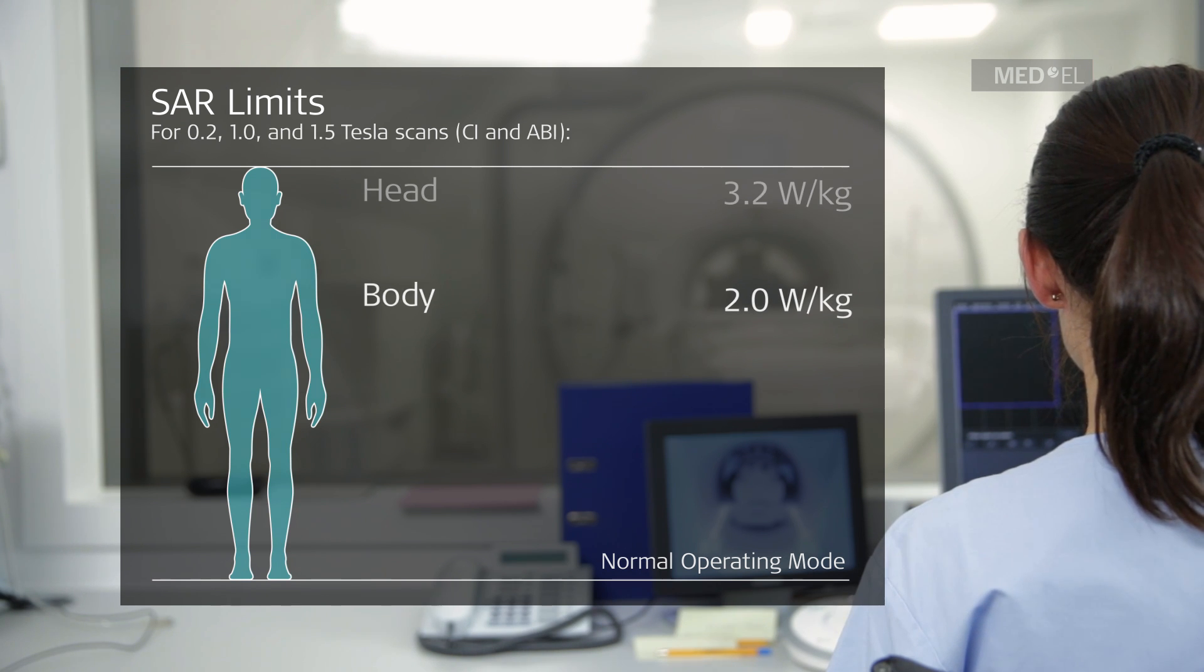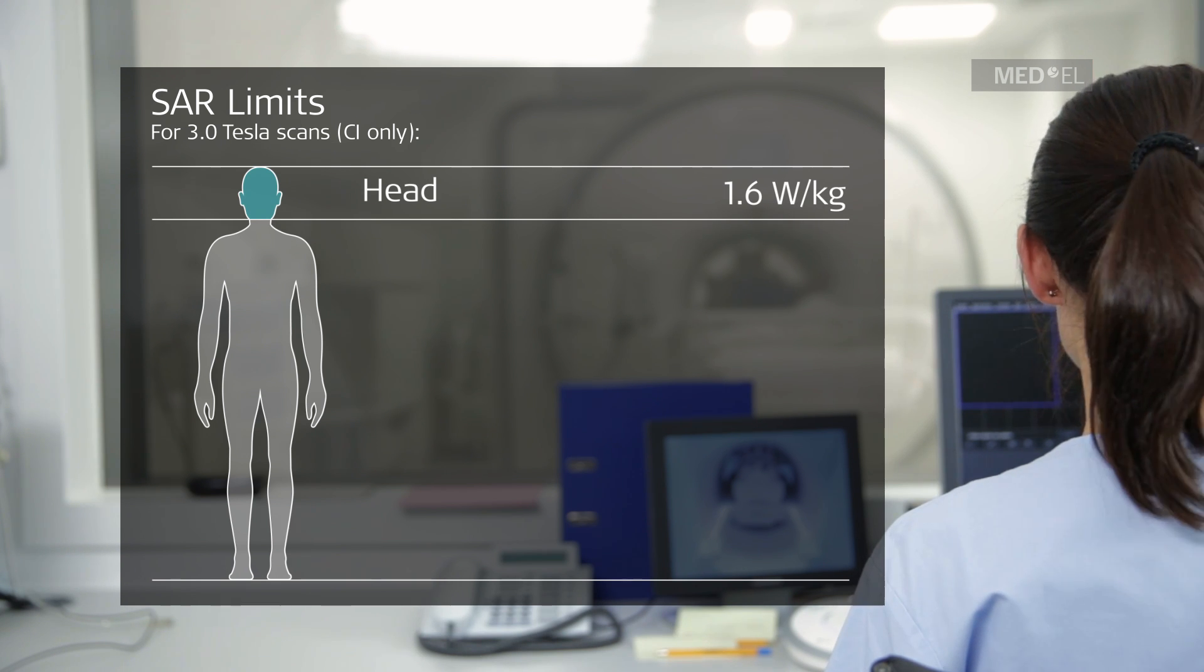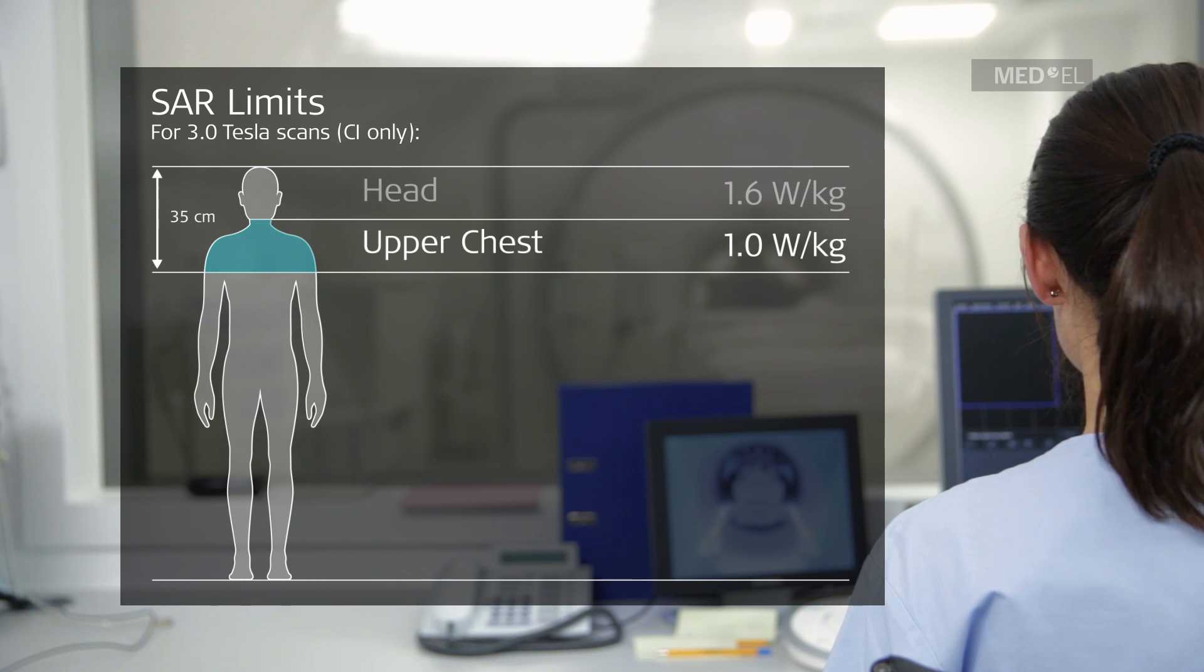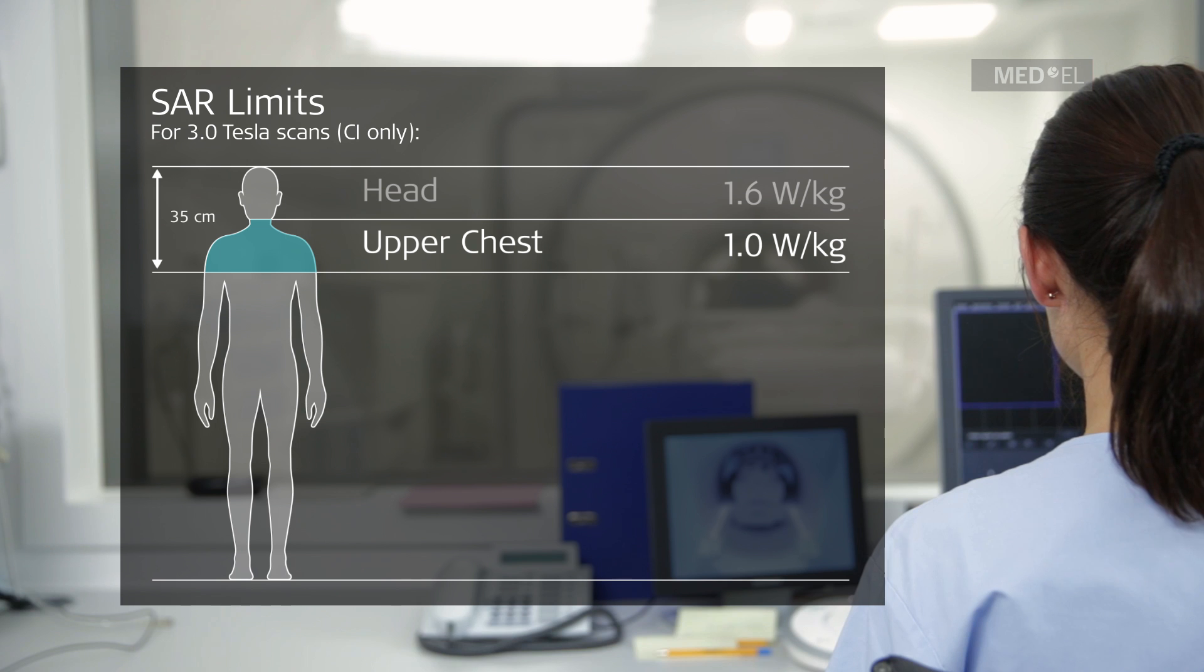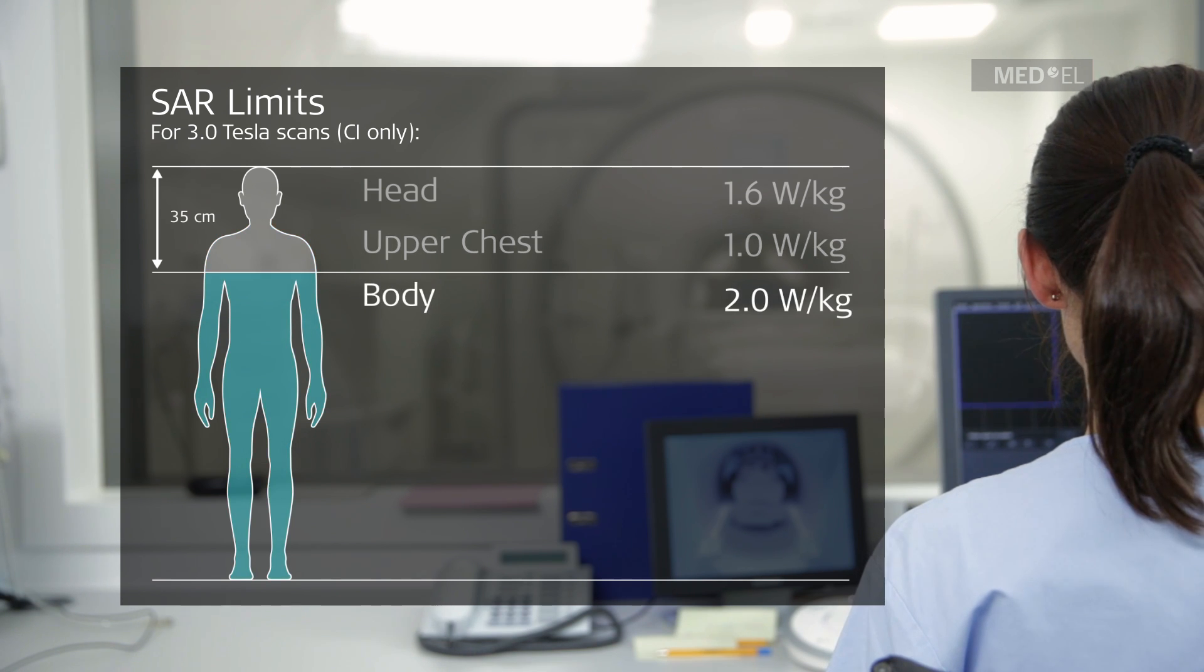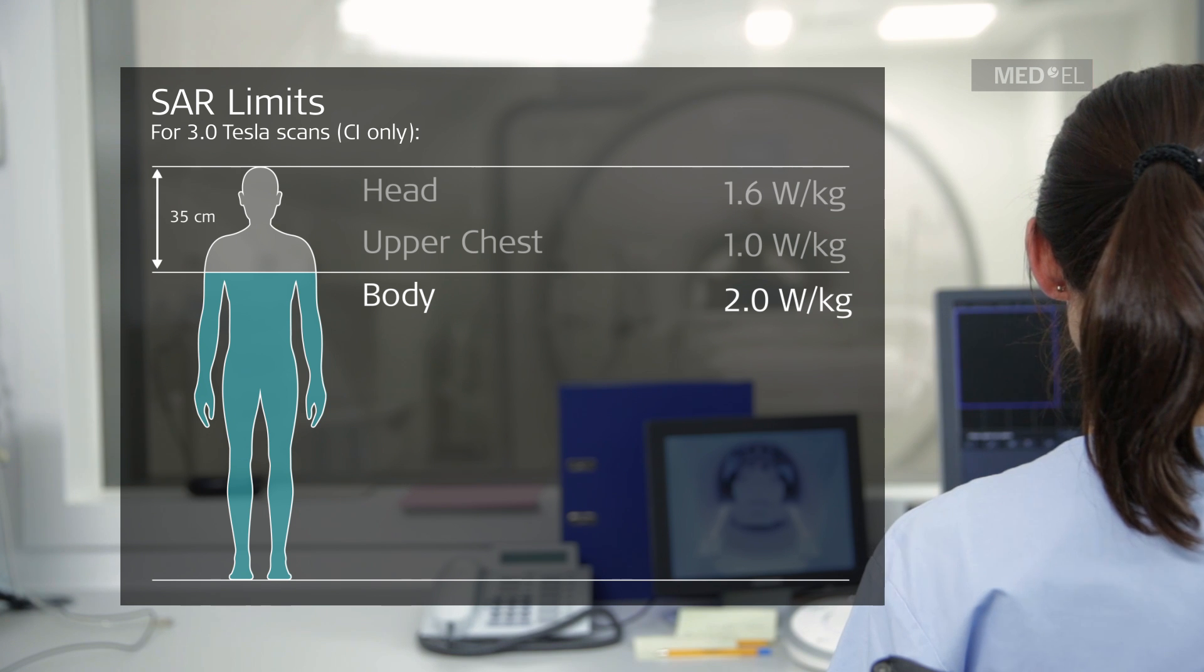For three Tesla scans with a synchrony cochlear implant, the SAR limit is 1.6 Watt per kilogram for the head. The whole body SAR limit is 1 Watt per kilogram for body regions less than 35 cm from top of the head and 2 Watt per kilogram for body regions more than 35 cm away from top of the head. Please note, the synchrony auditory brainstem implant is only approved for 0.2, 1, and 1.5 Tesla MRI.